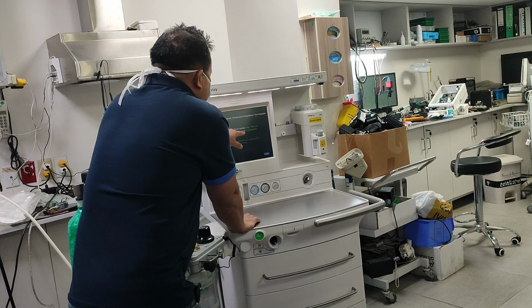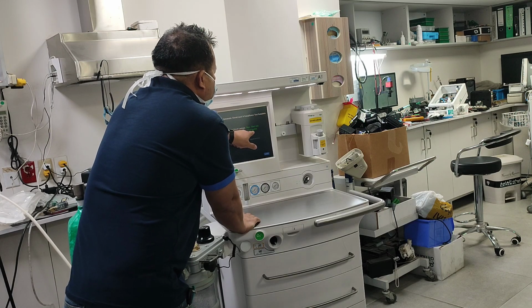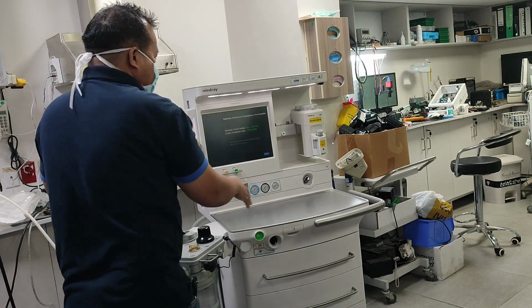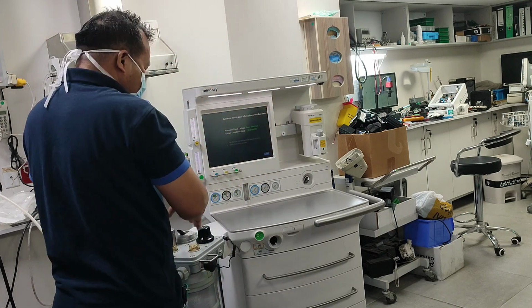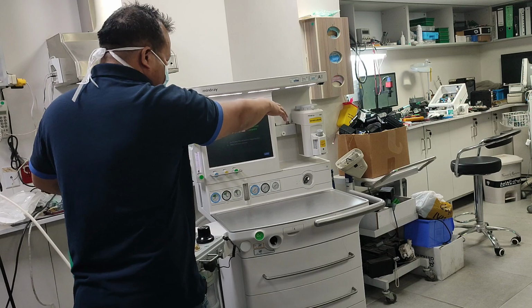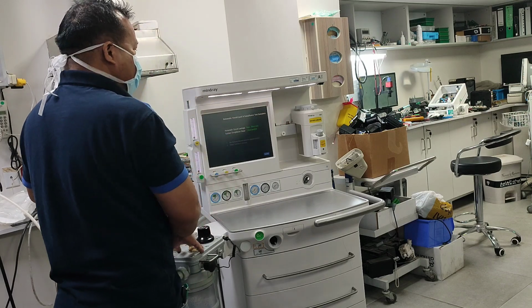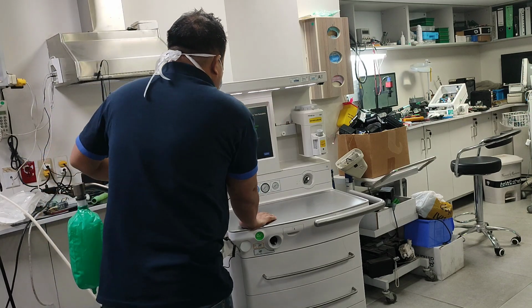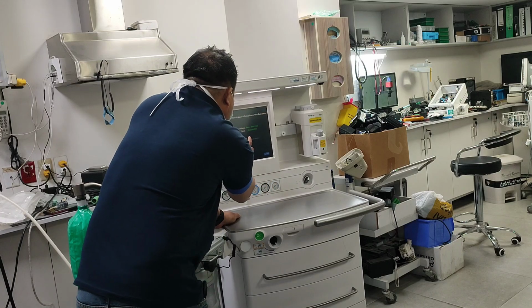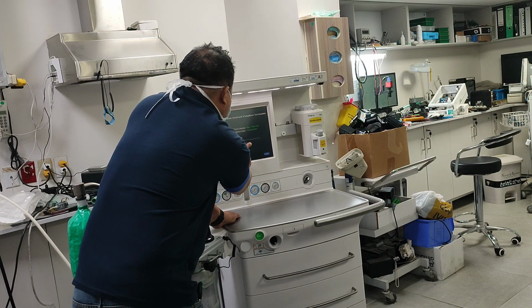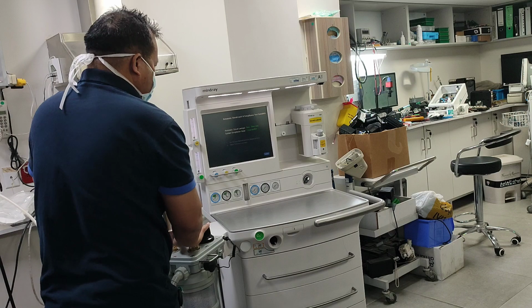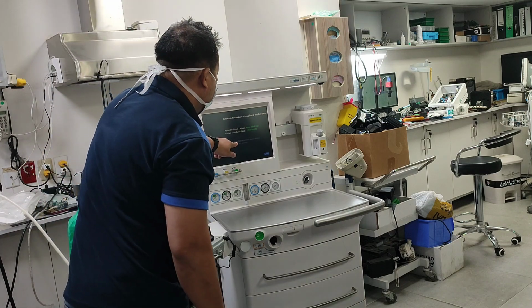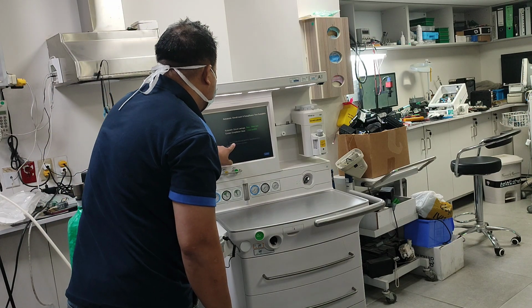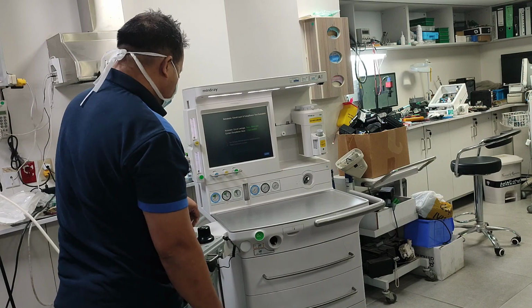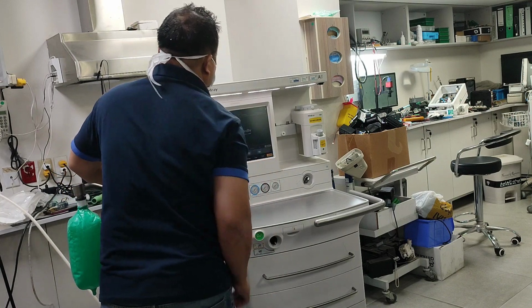The system compliance value is 1.4 ml per centimeter of water. It's very minimal also, 1.4 only in the system. The system is complete here, including the patient module. So here it says to set the auto manual switch to manual position and select to continue. Set the auto manual switch to manual position and select continue.